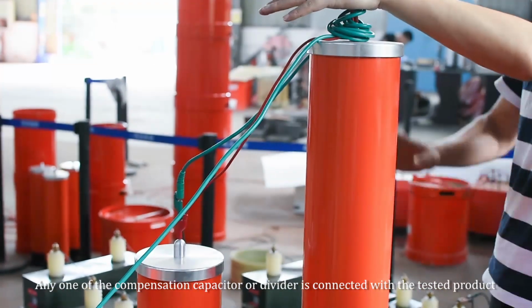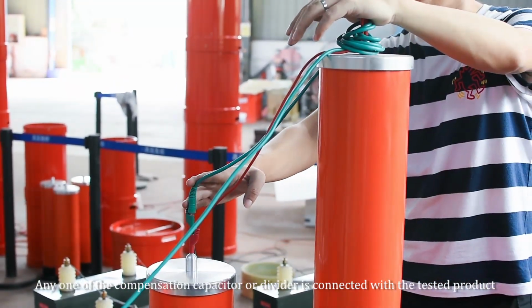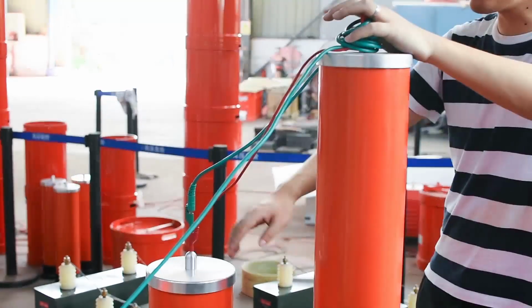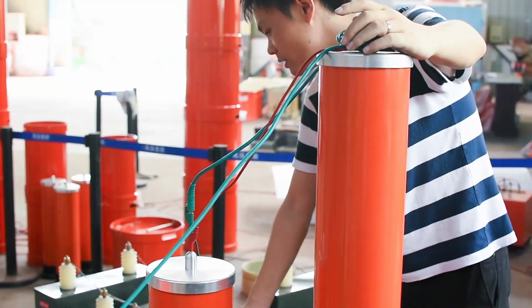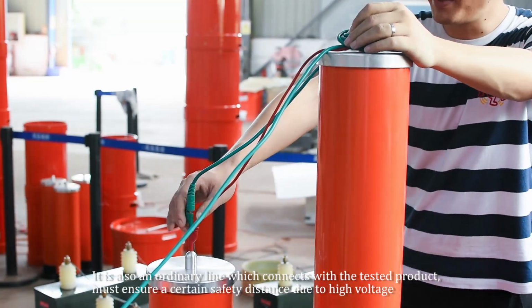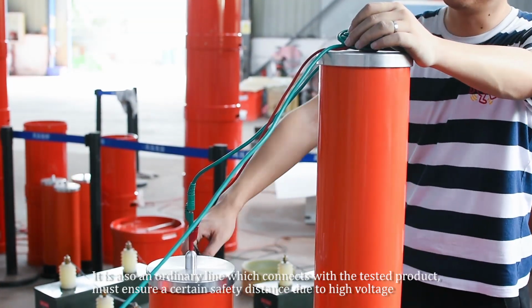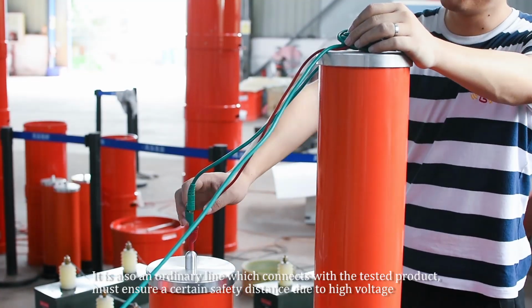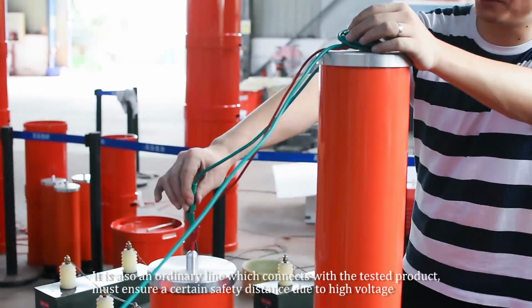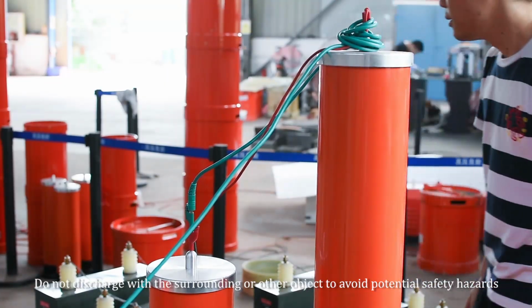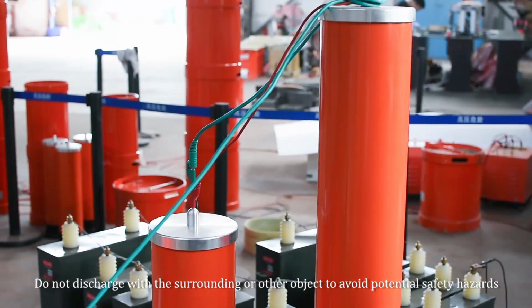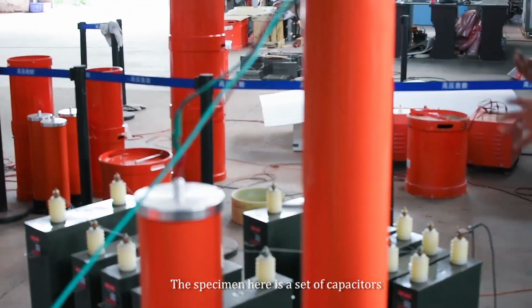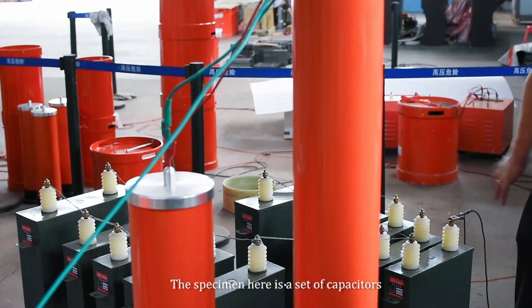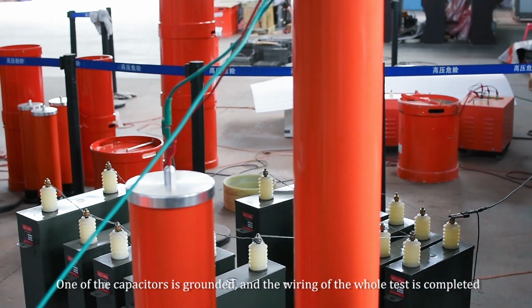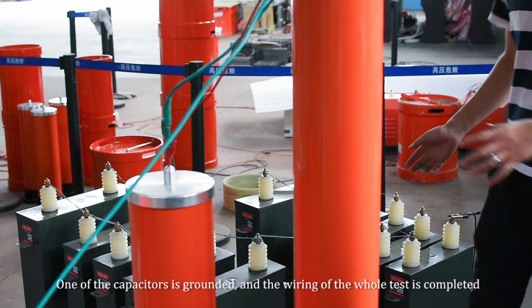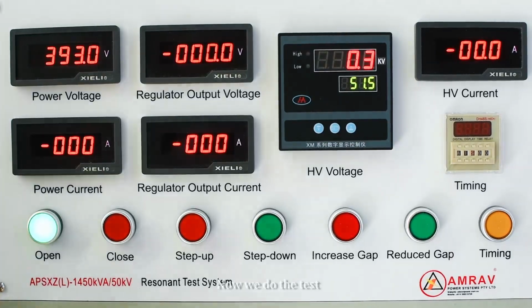Either the compensation capacitor or the divider is connected with the tested product. It's also an ordinary line which connects with the test product. Must ensure a certain safety distance due to high voltage. Don't discharge with the surrounding or other objects to avoid potential safety hazards. The specimen here is a set of capacitors. One of the capacitors is grounded, and the wiring of the whole test is completed. Now we do the test.